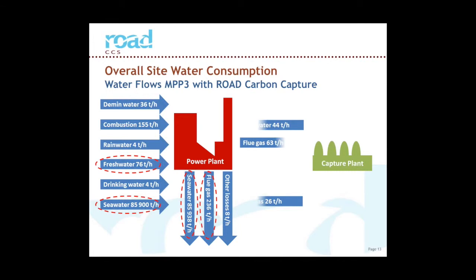We also see a reduction in the seawater usage because we've diverted steam away to the capture plant, and so we've reduced the cooling demand of the main power station. The capture plant is reducing the water in the flue gas because of the quench in the DCC. It comes back at between 30 and 35 degrees or thereabouts from the capture plant, and it's had a lot of the moisture removed. So the water in the flue gas has also dropped coming out of the whole process.